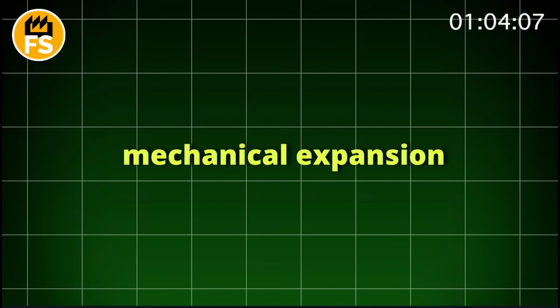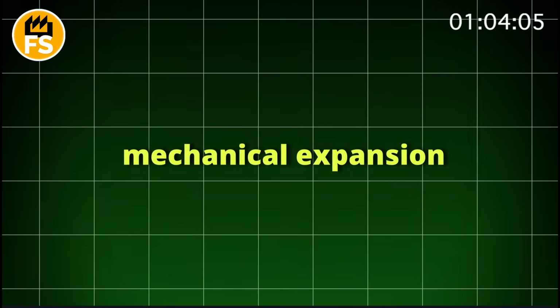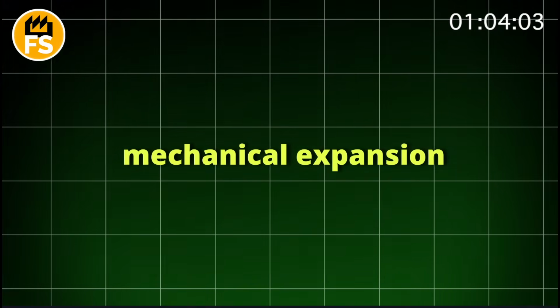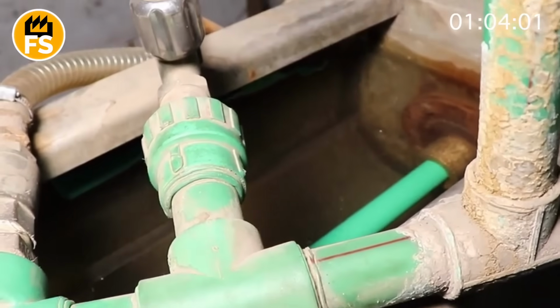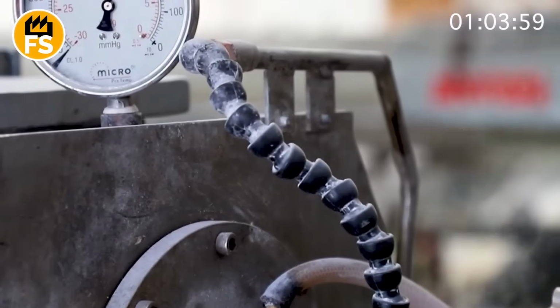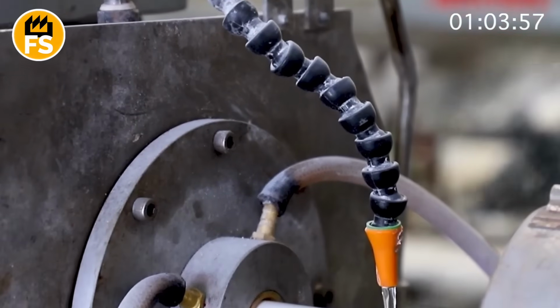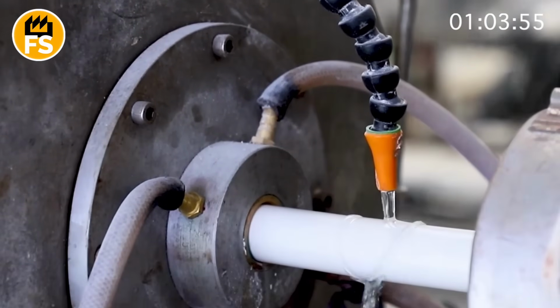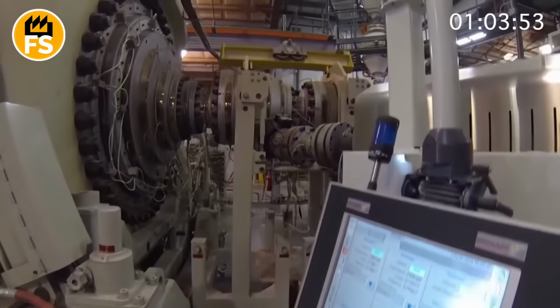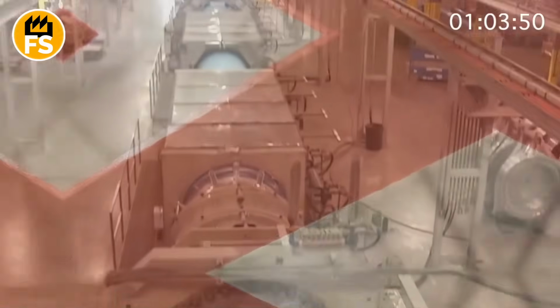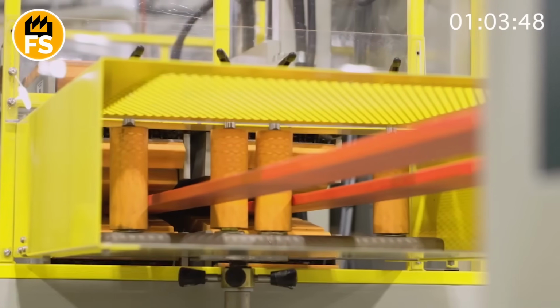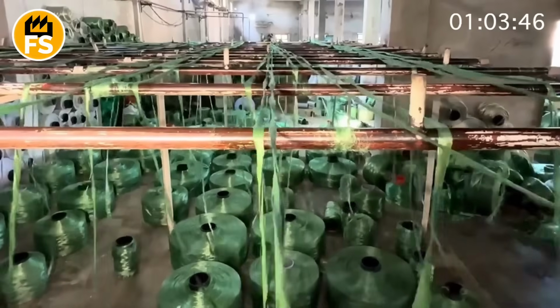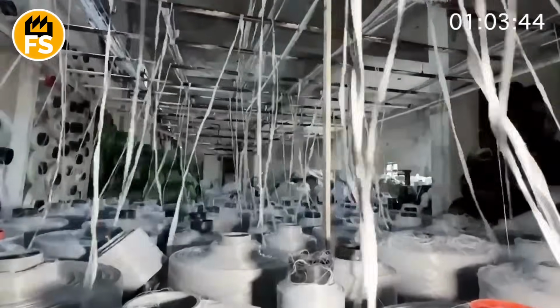After stringing, mechanical expansion begins, a unique procedure where special mandrels are inserted into the tubes, or they are pressed from the inside with hydraulics. This expands the copper, and it presses tightly against the holes in the fins. The contact must not just be tight, it must be perfectly tight, because this is the area where heat will be transferred from the hot fluid to the cooling air or vice versa. Every microcrack is a loss of efficiency.